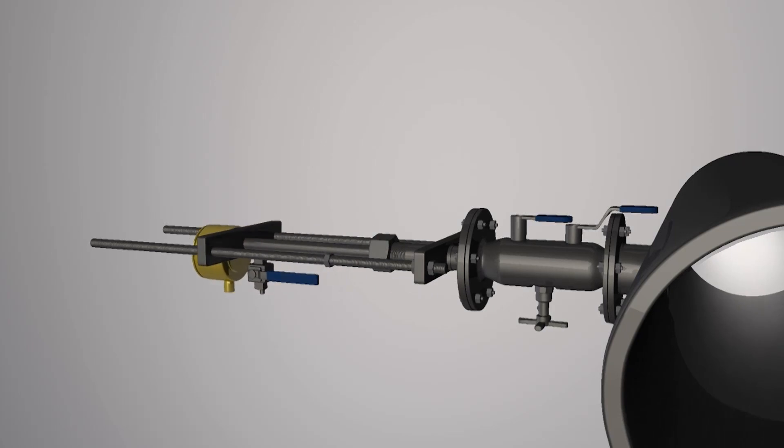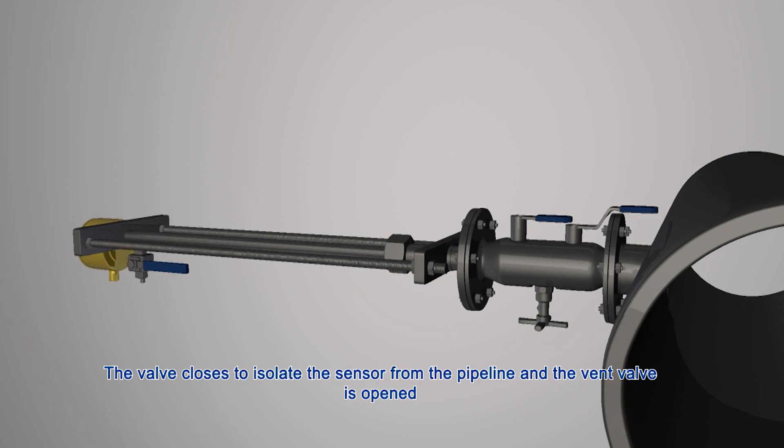VeriCal procedure. The packing gland loosens to allow the sensor to be retracted back through the valve. The valve closes to isolate the sensor from the pipeline and the vent valve is open.